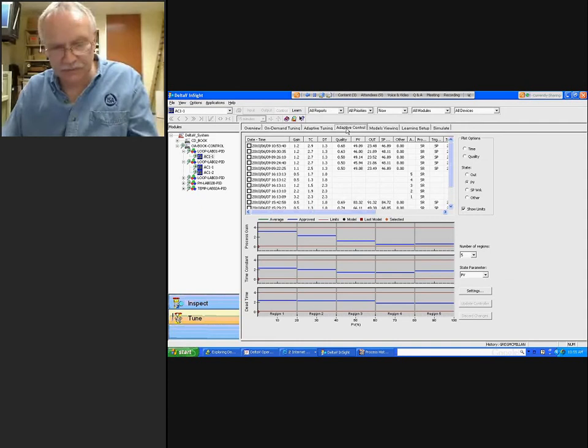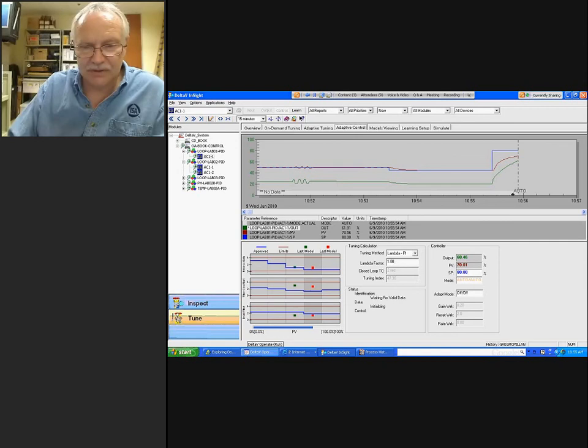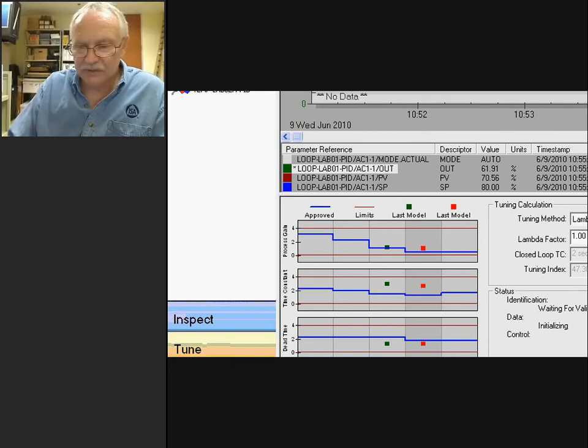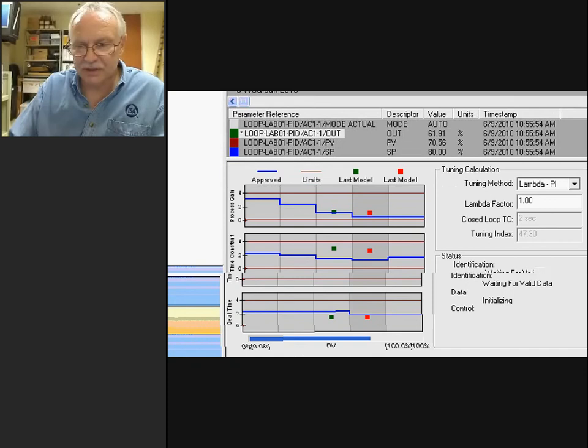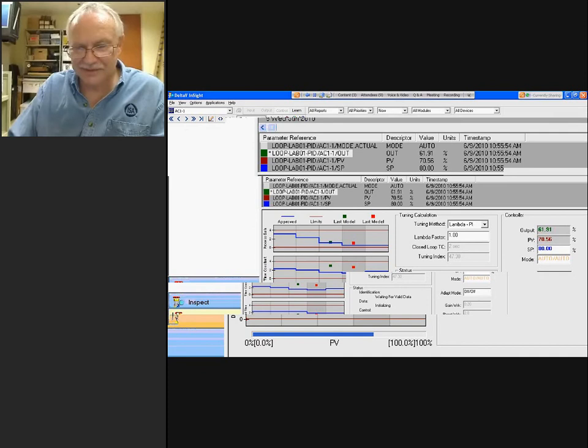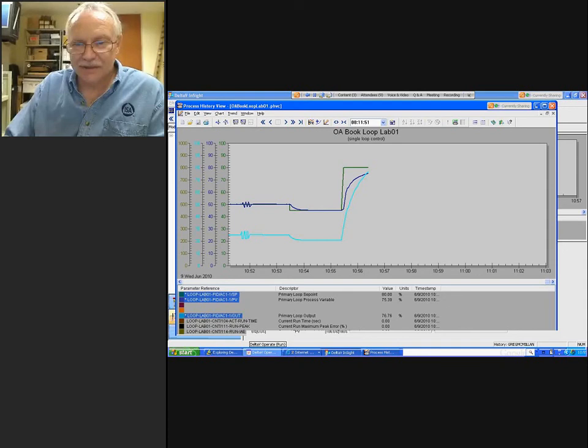we see that the process gain for low pressure set points is up over 3, and is getting close to like 0.2 if we get to the flat part of the pump curve, which is the case for the high pressure set points. And we still haven't gotten there, so let's go back and we'll look at model viewing.